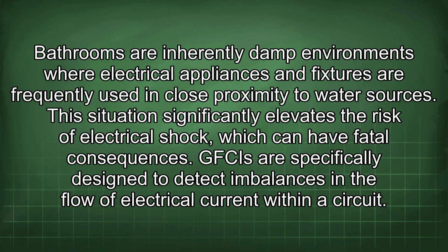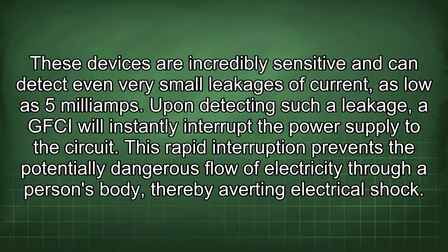GFCIs are specifically designed to detect imbalances in the flow of electrical current within a circuit. These devices are incredibly sensitive and can detect even very small leakages of current, as low as 5 mA. Upon detecting such a leakage, a GFCI will instantly interrupt the power supply to the circuit. This rapid interruption prevents the potentially dangerous flow of electricity through a person's body, thereby averting electrical shock.